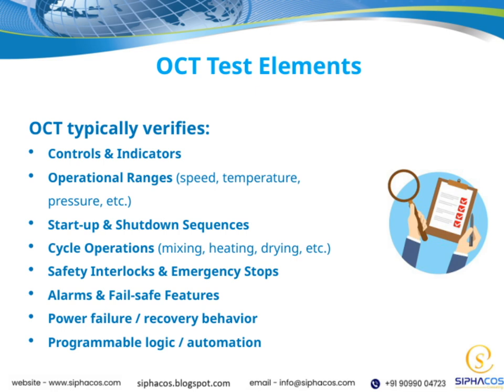Alarms and fail-safe features are also examined. These alert us to issues early on or shut down processes safely if a fault occurs. Power failure and recovery behavior are tested to see how the system responds during outages and how quickly and safely it recovers once power is restored. We also evaluate programmable logic and automation systems, making sure the control logic is correct and that the system responds appropriately to various inputs and conditions.